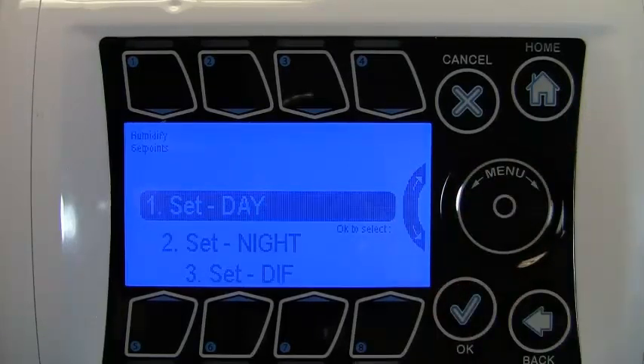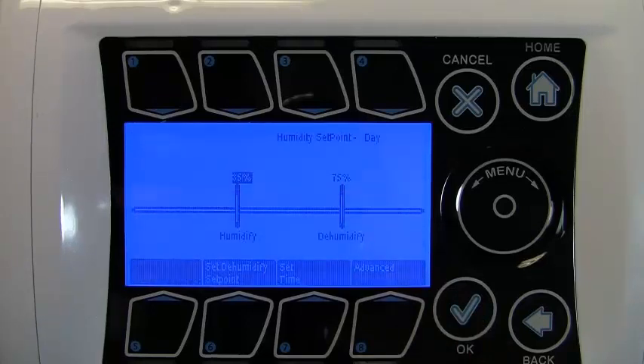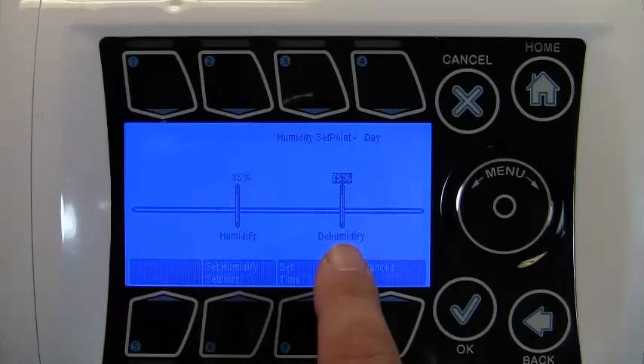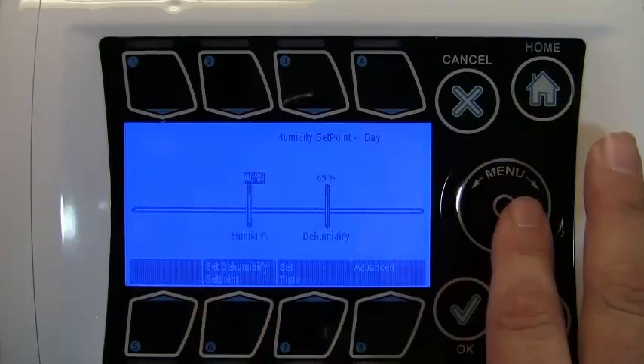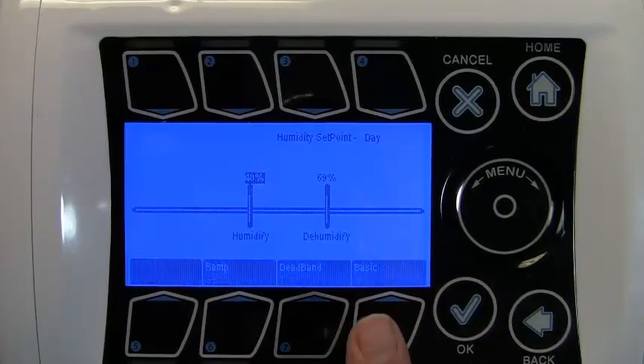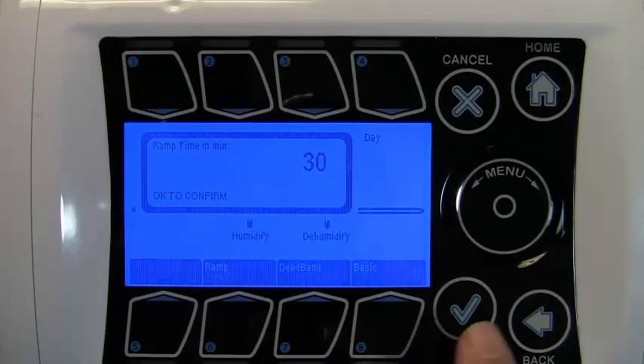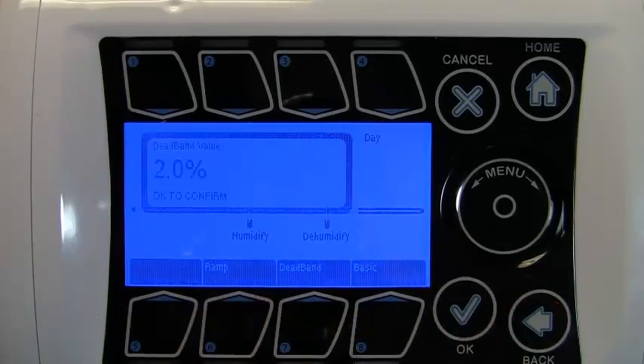Now we're going to talk about humidity set points. Go into humidity set point and you'll find the same three options: day, night, and DIF. Going into day, you'll see the same basic set point menu system for humidity. Button six allows you to navigate between setting your humidity and dehumidity percentages. For instance, it currently says dehumidify 75% — we're going to bring that down to 69. You can also raise the humidity set point. Pressing advance brings you to the ramp, which is a gradual humidity transition from one set point to the next — set to 30. You can also set the dead band, which prevents equipment from oscillating back and forth due to small humidity fluctuations.